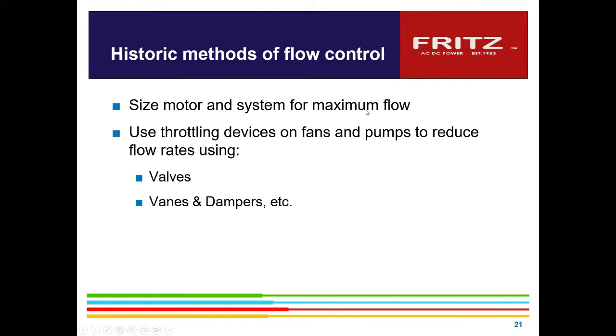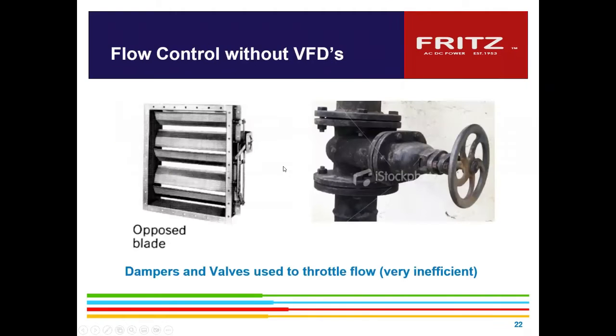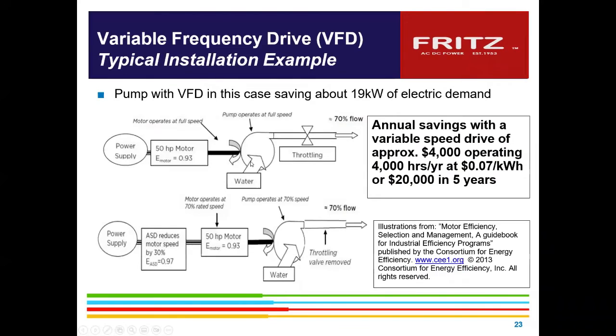And then they size the motor for maximum flow, and then they use throttling devices to reduce that flow, those being valves, dampers, et cetera. So inside buildings, you'll find several valves, and a lot of times those are turned down to maybe 30, 40, 50% flow through, but the motor is sitting out there pushing full power. Or they have dampers in the system, and they're dampering the output flow, but the fan is still running over there at full speed.